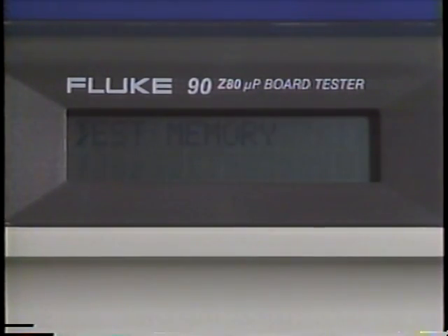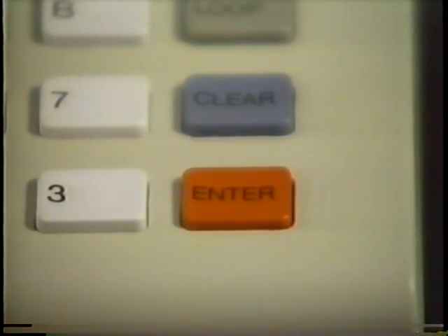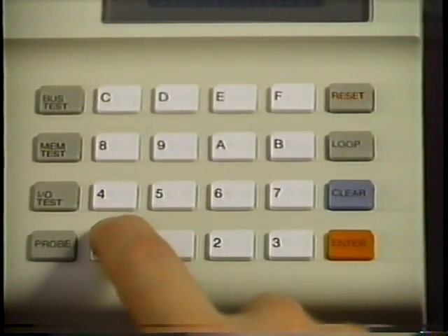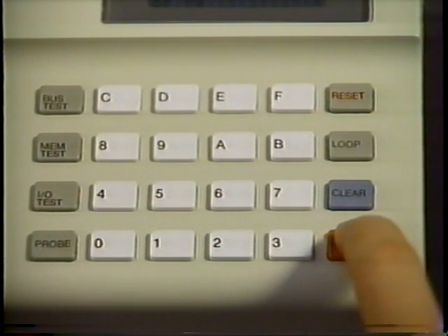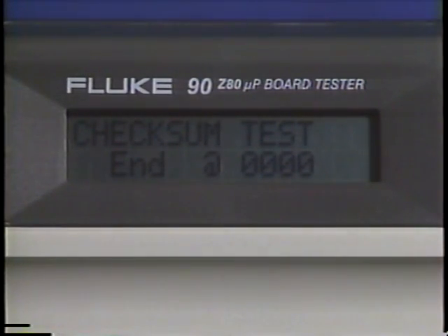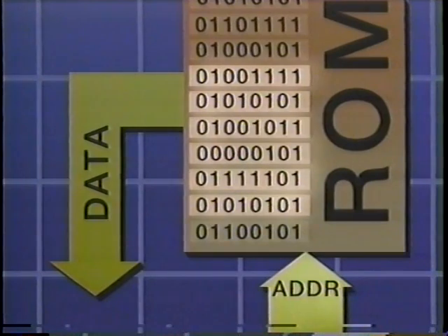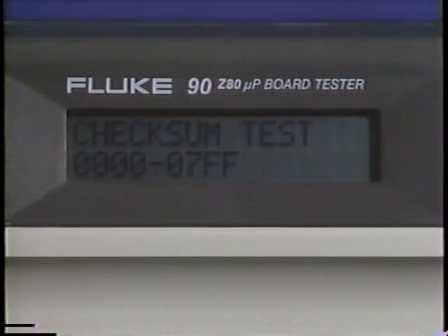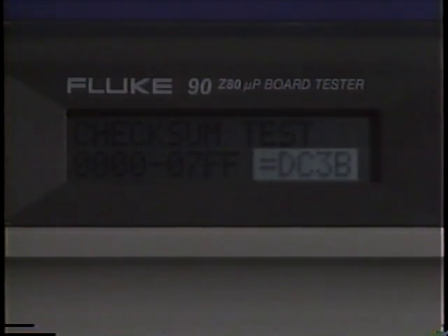Memory checksum should be used to test the UUT's ROM. As you did before, press the Memory Test key to scroll to the desired test. Then press Enter. To specify the test range, select the start address and press Enter. Select end address in the same way and press Enter once more. The Fluke 90 will now sum all data in the specified range, then display the total. This figure will equal the sum generated by most EEPROM programming equipment.